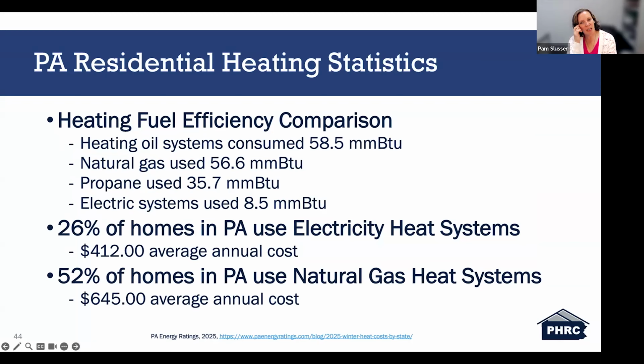So taking a closer look at heating fuel usage and cost trends across Pennsylvania can help to better understand the practical implications of switching to more efficient systems like heat pumps. Heating fuel efficiency comparison here, heating oil systems consumed 58.5 million BTUs is what the data showed. And this data all came from PA Energy ratings of 2025. Natural gas, they showed, used 56.6 million BTUs. Propane used 35.7. Electrical systems, they showed, used 8.5.